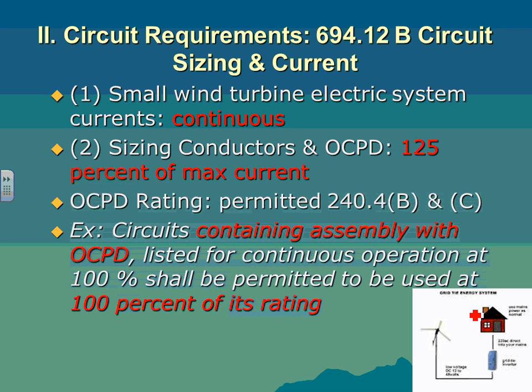Do you guys remember what these are? For the electricians, again, these are a little bit too much into the detail. If you end up with a non-standard overcurrent device, then you can't go to the next standard. For example, this is where you can get a 500 kcmil conductor to feed a 400 amp panel, even though 500 kcmil can give you 380 amps. So what happens with the 20 amps? Exception in the code, exception B, tells you no problem, as long as you don't touch the ceiling of 800, your overcurrent device can be slightly higher than your conductor. So they are saying the same thing, this will apply to it.